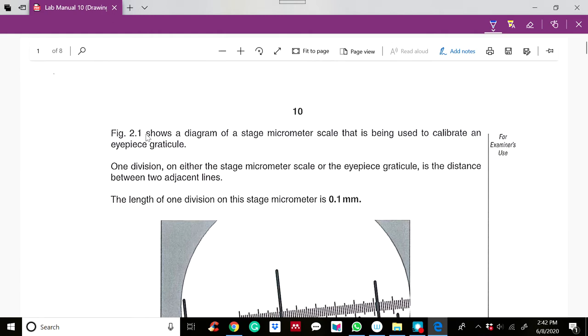Figure 2.1 shows the diagram of a stage micrometer scale being used to calibrate an eyepiece graticule. When referring to divisions on either the stage micrometer scale or the eyepiece graticule, it is the distance between two adjacent lines. The length of one division on this stage micrometer is 0.1 mm.